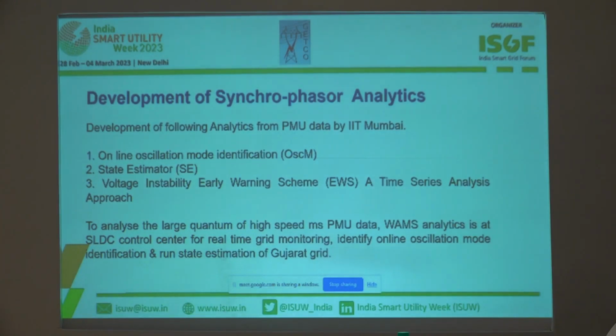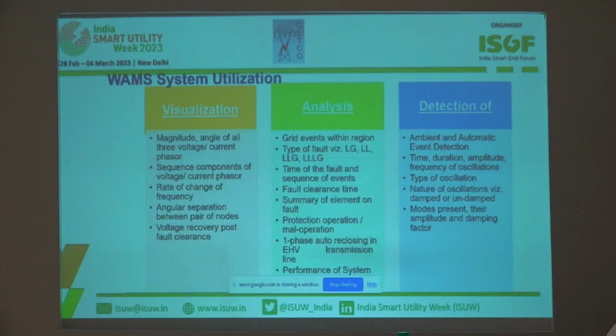This analytics we are using day by day in our control room for visualizing magnitude and angle of all 3 voltage, current phasors. We are getting sequential components at our control center. ROCOF, the rate of change of frequency, is continuously monitored based on this wide area monitoring data. We have divided our grid into 4 zones, and we are monitoring the angular separation, if any, between pairs of nodes, from south to west or west to north region.